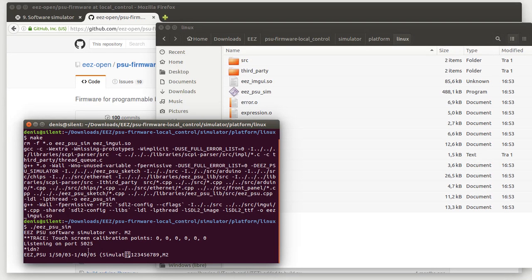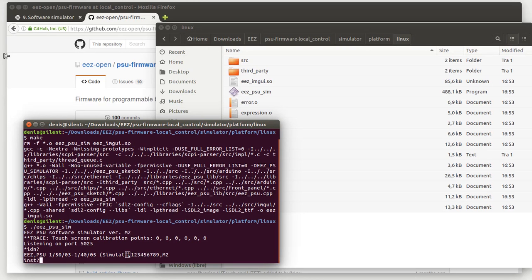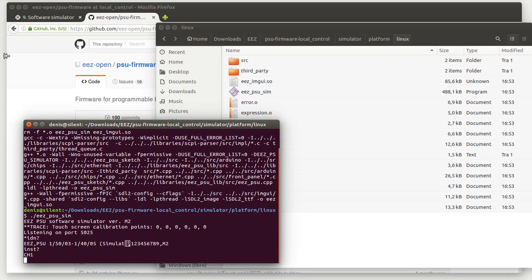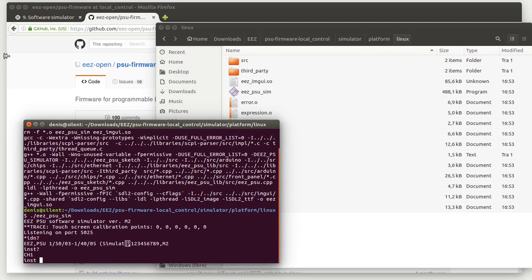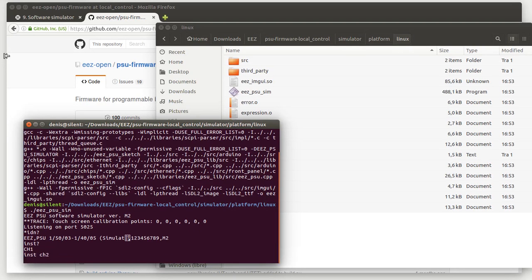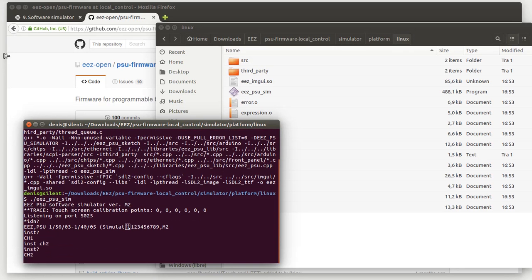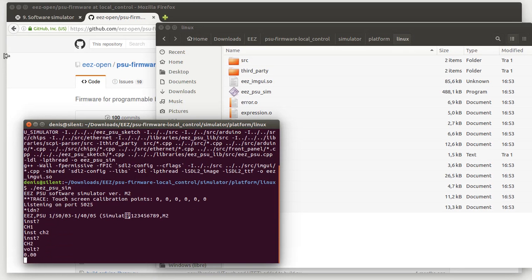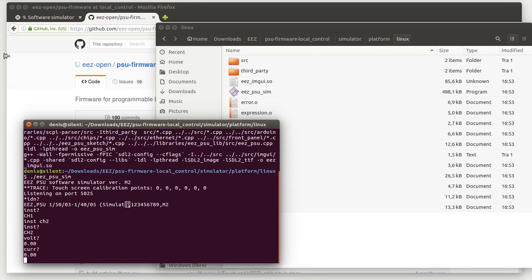So this terminal can be used as a console to test SCPI commands. For example, we can check what is the current instrument or channel. We can change it to someone else. We can check what is the voltage set - it's zero, and current - it's also zero. But there is one command...